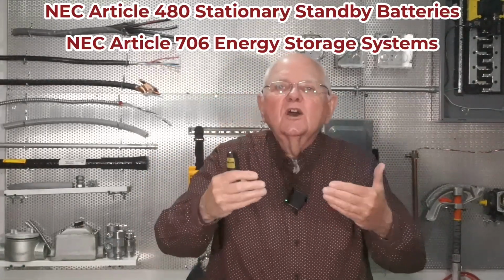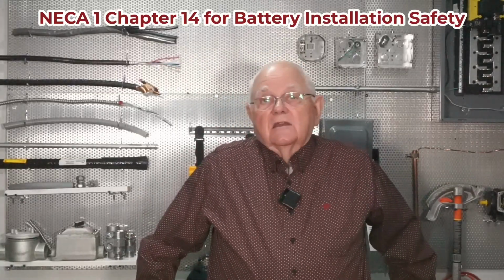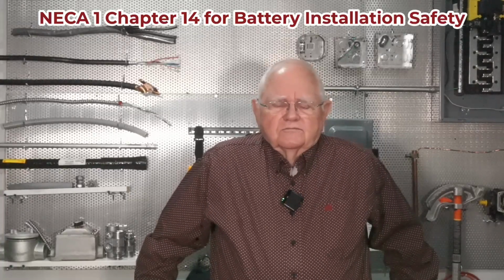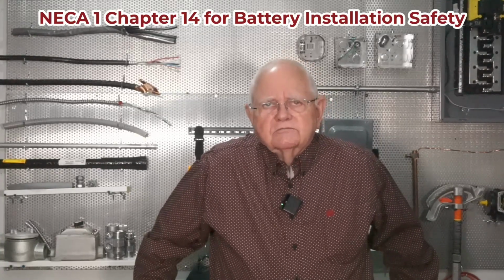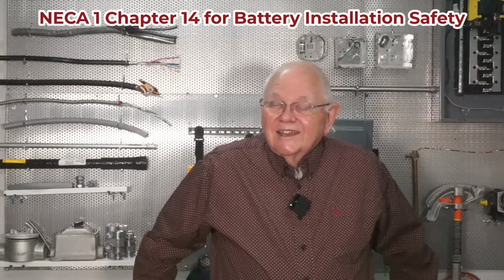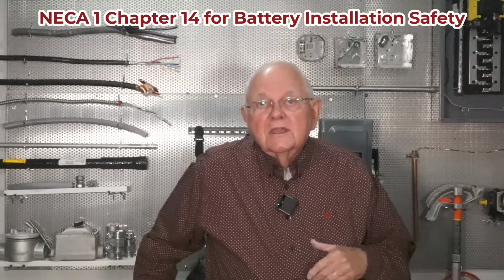But the way that NECA approaches this Chapter 14 on battery systems is safety. And it tells you, I can't turn a battery off, can I? There's no switch I can flip on a cell, and maybe that cell, I measure it and it's 2.25 volts or something like that. Great big old battery cell, right? And you go, well, that's way below 50 volts. That's a safe working voltage. It's only 2.25 volts or 2.5 volts or whatever it is. But what about the energy inside of that thing? If we were to accidentally get a wrench or something across those terminals, extremely dangerous.